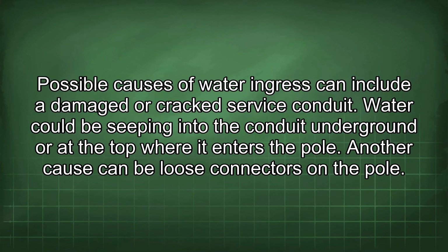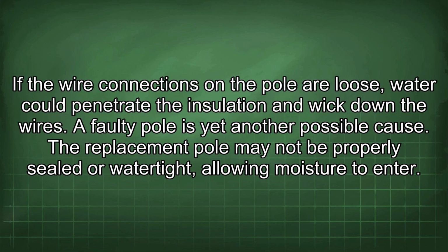Possible causes of water ingress can include a damaged or cracked service conduit. Water could be seeping into the conduit underground or at the top where it enters the pole. Another cause can be loose connectors on the pole. If the wire connections in the pole are loose, water could penetrate the insulation and wick down the wires.